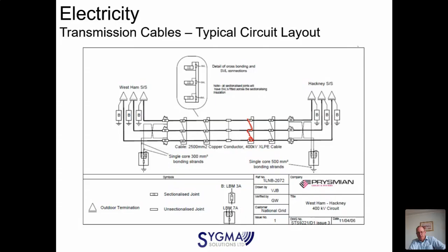The other issue is, I'll show you a picture of a joint bay in a minute, but at the joint bays, the cables are all connected together. You can see from that these links between the joints. So if you do manage to get a signal on one cable, and these cables are laid side by side, I'll show you a picture in a minute, you get a signal on one, it's going to transfer across to the other two. So we've tried all sorts to get decent traces on these, and sometimes you can only really trace them using high frequency, which is not the preferred method, but sometimes the only option. And of course, you've got no access to them, so it's naturally induction.